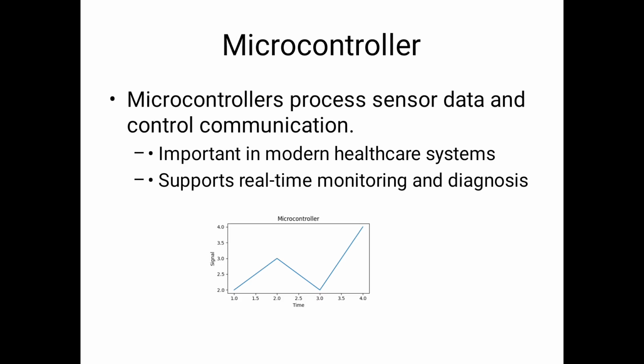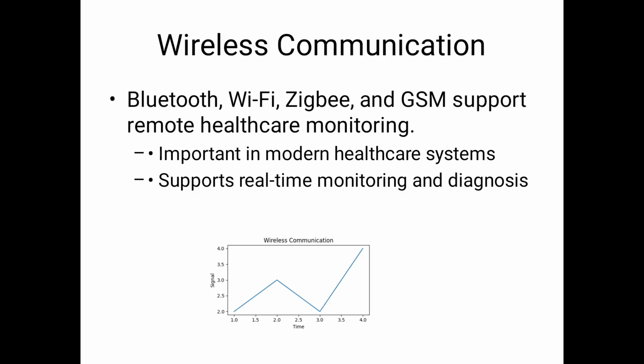Next, it is given to the microcontroller. The microcontroller is the heart of the embedded architecture. It functions as the central commander of the patient monitor. It uses the internal analog-to-digital converter to digitize the conditioned sensor waveforms. Then it is given to the wireless communication protocols.